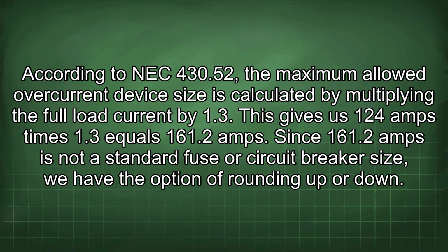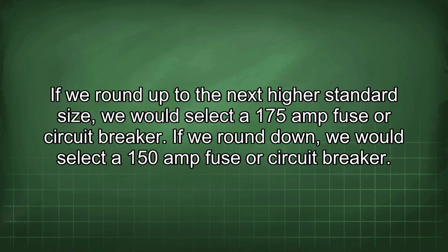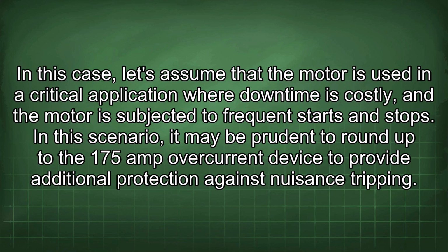Since 161.2 amps is not a standard fuse or circuit breaker size, we have the option of rounding up or down. If we round up to the next higher standard size, we would select a 175 amp fuse or circuit breaker. If we round down, we would select a 150 amp fuse or circuit breaker. In this case, let's assume that the motor is used in a critical application where downtime is costly and the motor is subjected to frequent starts and stops.